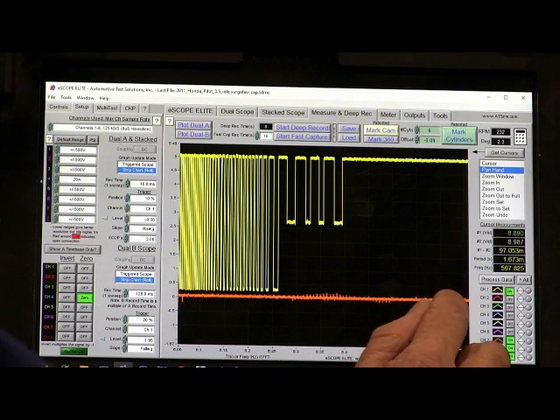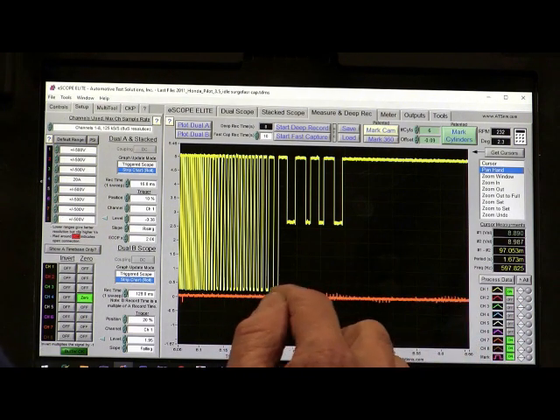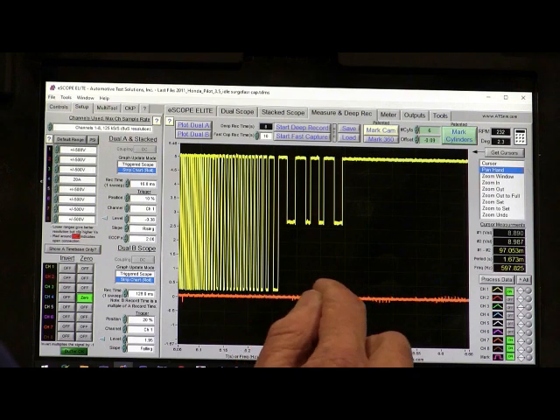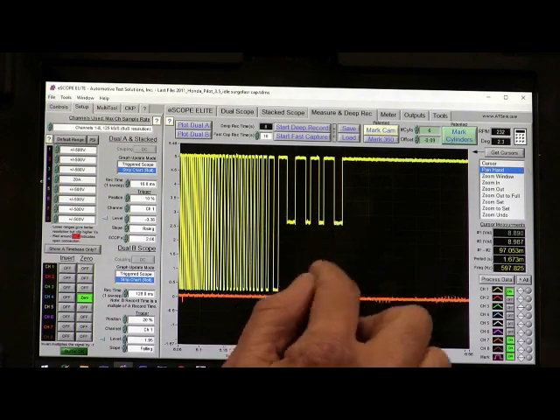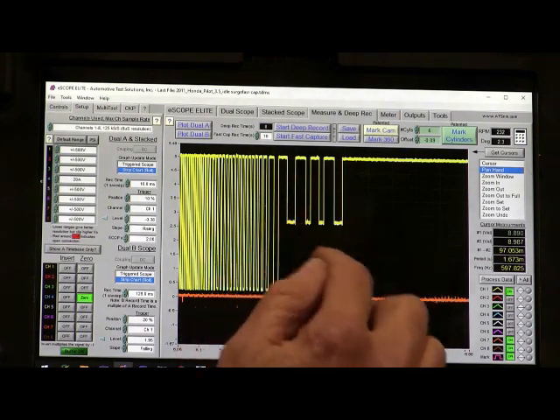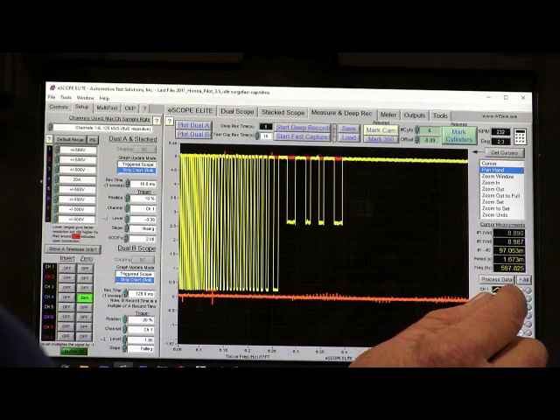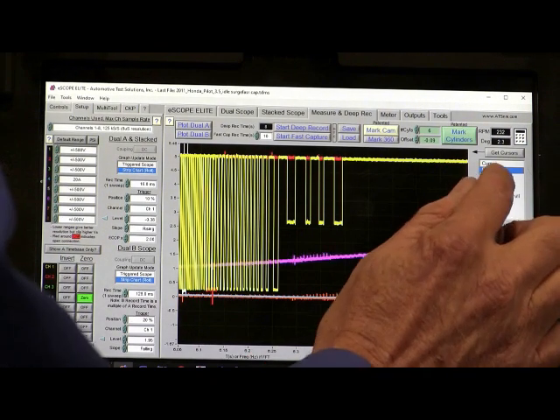That's my ground from that sensor, and the sensor ground did not go up. The sensor ground stayed good, and this pulled up. So that tells me that this is the sensor circuit failing itself. Let's turn this stuff back on, go back out.